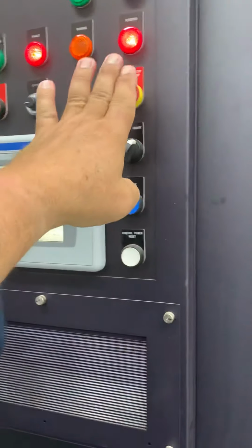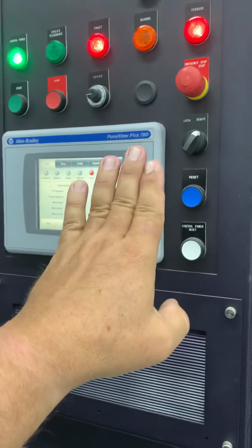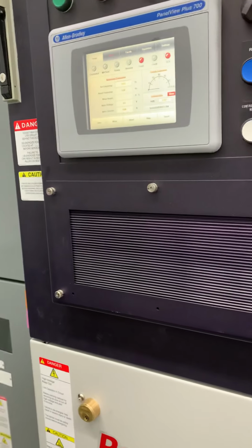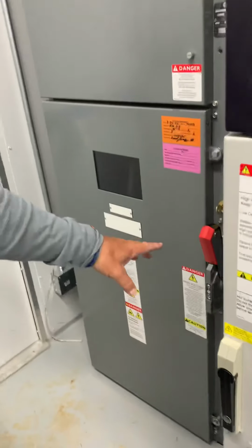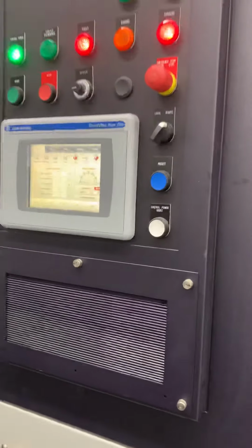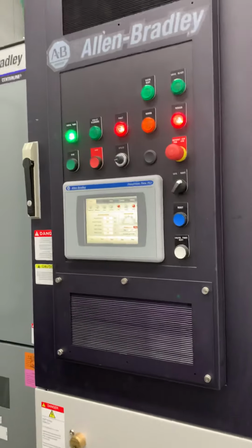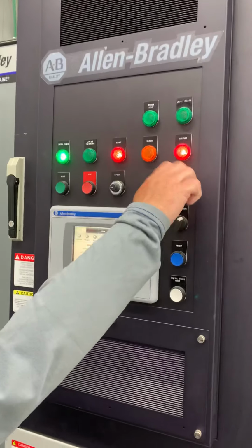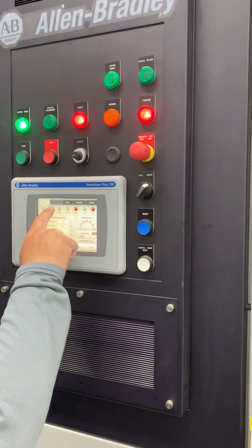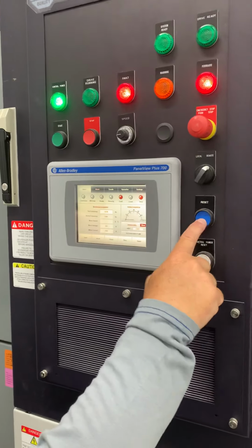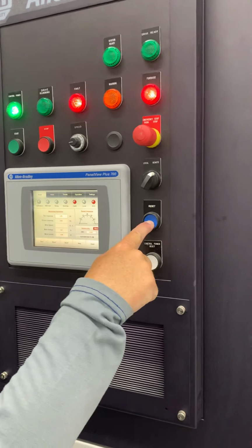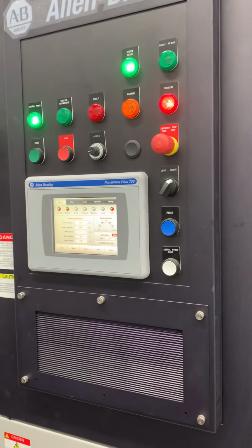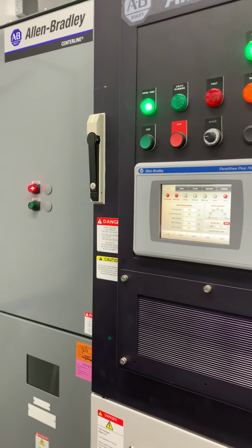What we should do is always, when not in service, just keep this e-stop depressed. You can leave that disconnect on, and there's no medium voltage on the drive until you pull the e-stop. So if you want medium voltage on the drive, pull the e-stop, and see how it has blinking alarms. Hit reset, hold it in, and that energizes the drive.